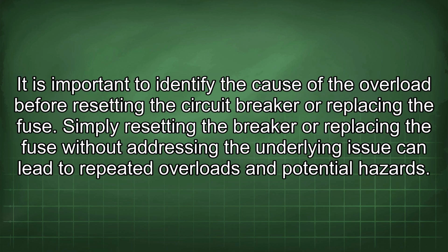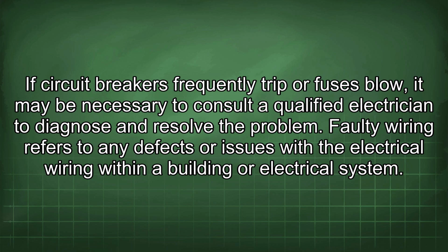It is important to identify the cause of the overload before resetting the circuit breaker or replacing the fuse. Simply resetting the breaker or replacing the fuse without addressing the underlying issue can lead to repeated overloads and potential hazards. If circuit breakers frequently trip or fuses blow, it may be necessary to consult a qualified electrician to diagnose and resolve the problem.